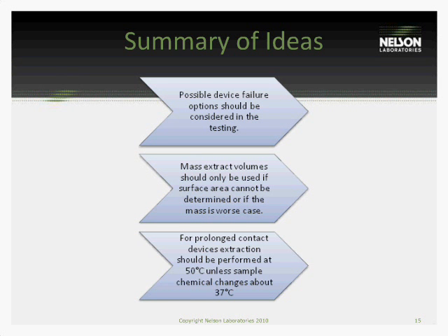So the FDA has been asking us to elevate the temperature to get a prolonged exposure. My suggestion is that unless your device changes chemically at 37, just do 50 regardless of duration, because it's worst case, most devices will handle 50 degrees Celsius well, and you don't have to worry about trying to answer that 37-degree question.